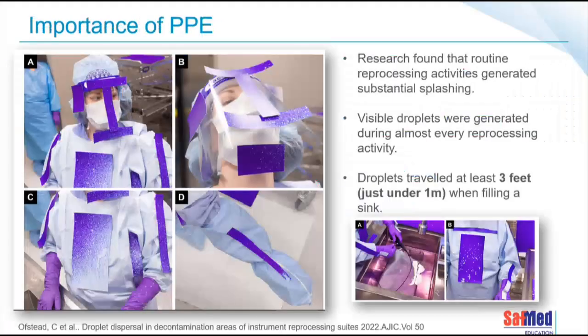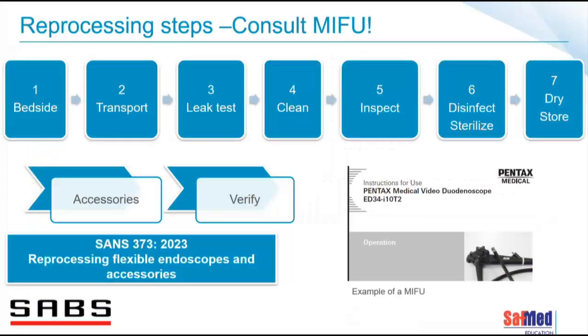Don't forget to don your PPE. Now, research found that routine reprocessing generated substantial splashing, specifically when reprocessing scopes, and visible droplets were generated quite far distances, just under a meter, just by simply filling the sink when you're washing the scope. Please be very cautious and make sure you're wearing PPE. Now remember, before reprocessing any scope, it is absolutely critical, repeat that, absolutely critical, that you consult the manufacturer's instructions for use for your particular make and model of scope that you are going to clean.